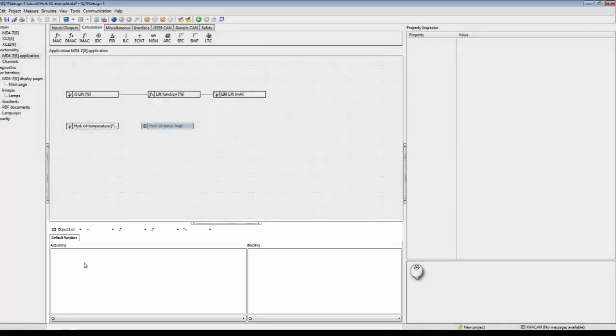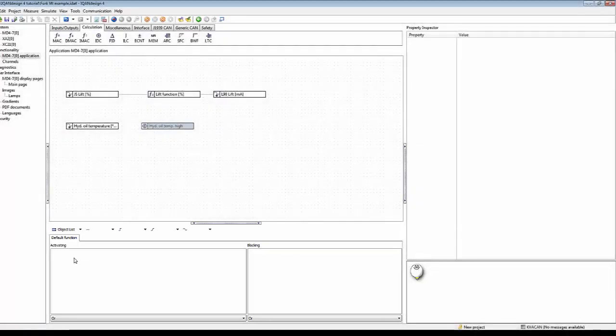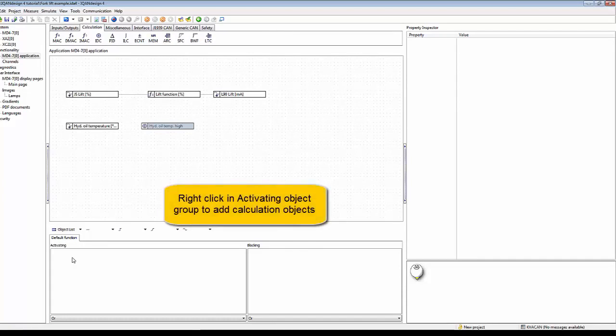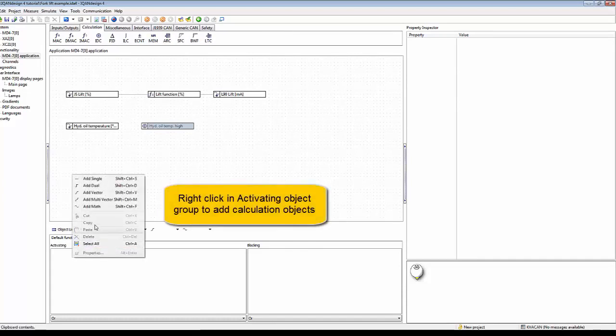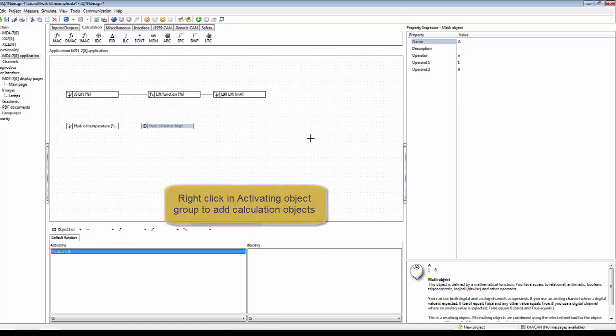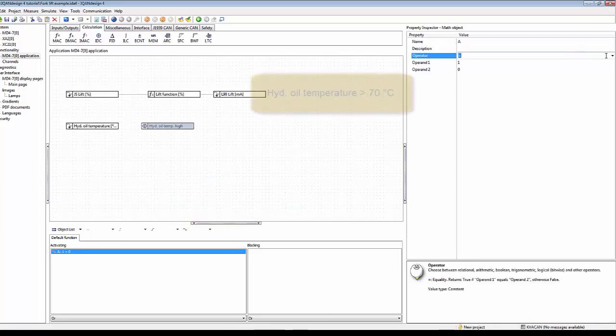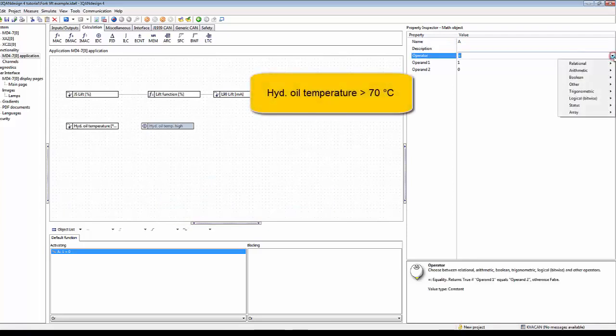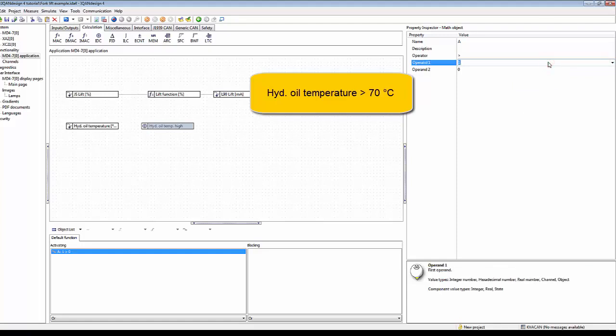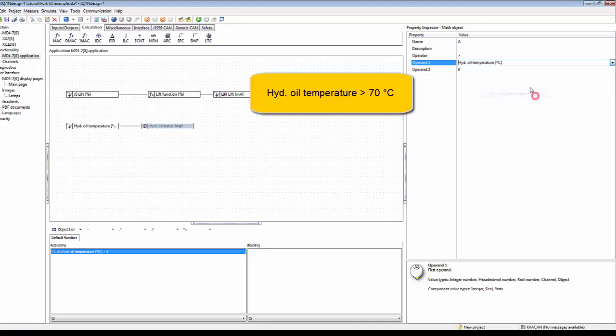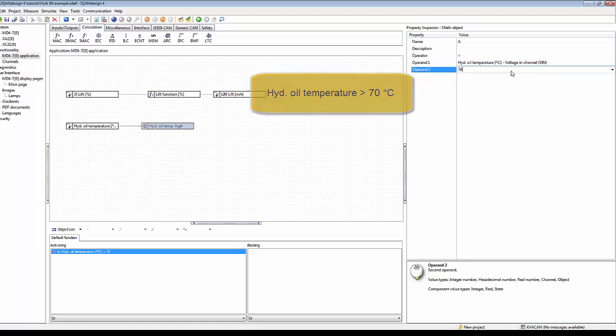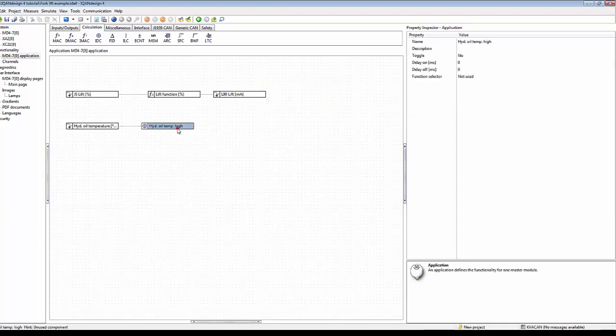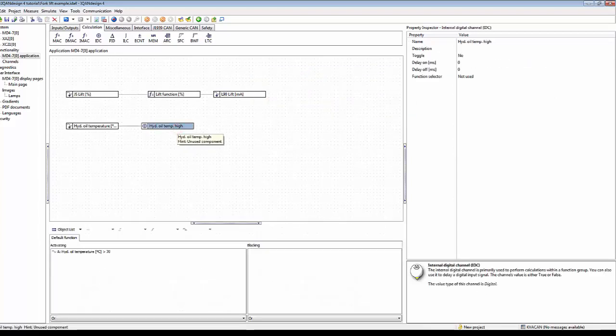To add the logic, I can right-click in here and add a math function. I can select an operator relational larger than. Here my operand one is the hydraulic oil temperature, and operand two we can put this at maybe 70 degrees Celsius. Now we can go back to our main page here and connect it to the input channel here. Now we're ready to simulate this first part.